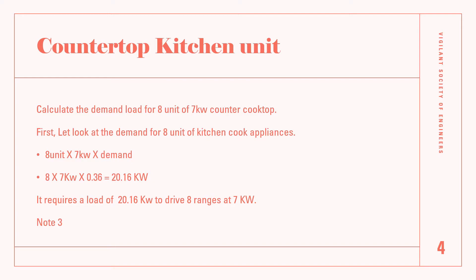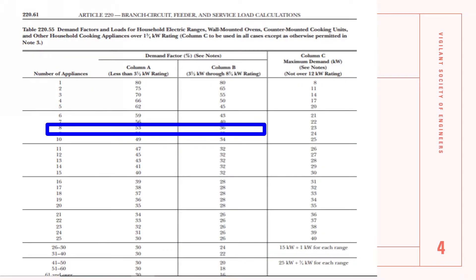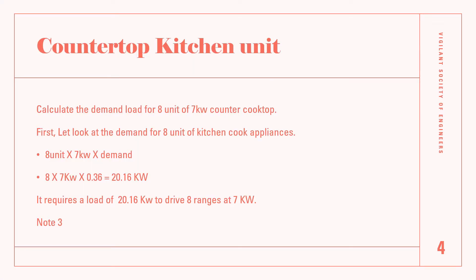The next question: what is the demand for eight units of seven kilowatt countertop cooktops? We have eight units times seven kilowatt times the demand factor. We go to Table 220.55, find the demand for eight units at seven kilowatt. This value is extrapolated from column B and we get 20.16 kilowatt required as the load for eight ranges at seven kilowatt.